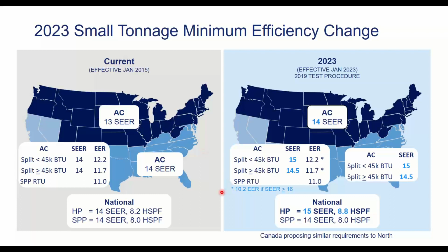Generally speaking, for cooling stuff, the full load efficiency requirements are probably never going to really go up again because we're kind of capped out. Generally speaking, the whole country wants all the things they replace to fit in the same place the old thing fit. And the best way to get a higher full load efficiency is to get more coil surface area, but nobody wants that. So we're dictating everything on part load efficiency, which means we can do it with ways other than surface area. Fan speed control being a big one of those. So all those are changing.